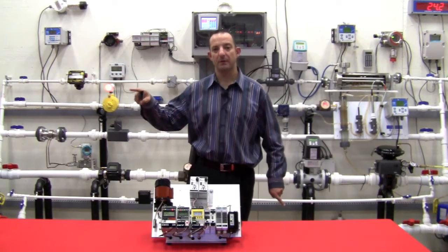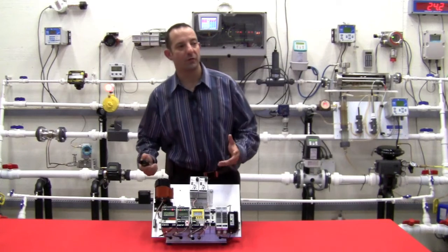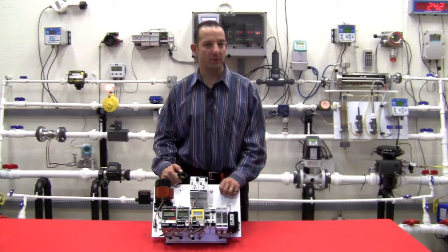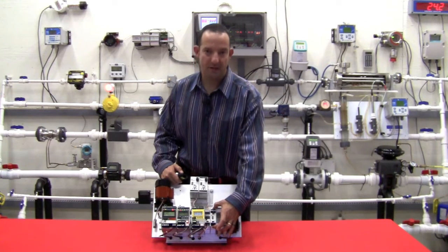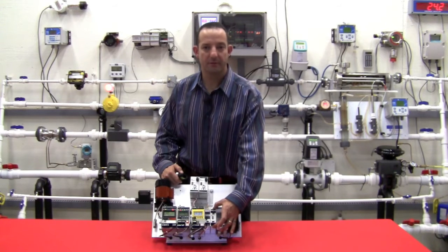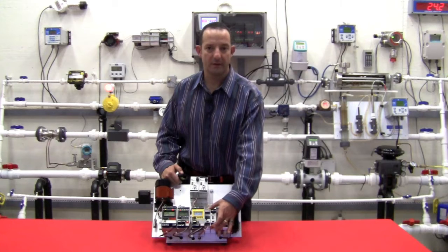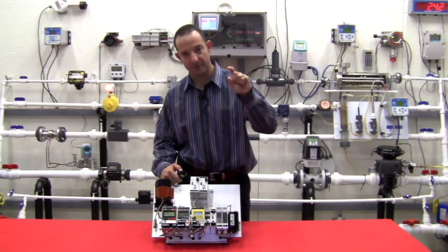range of the sensor. To give you an example, let's assume we're measuring a temperature with a span of 0 to 300 degrees Fahrenheit with a J-type thermocouple. We can calibrate the transmitter for 0 to 300 degrees Fahrenheit and concentrate all 18 bits of our input accuracy of that temperature transmitter in that 0 to 300 degree F span.